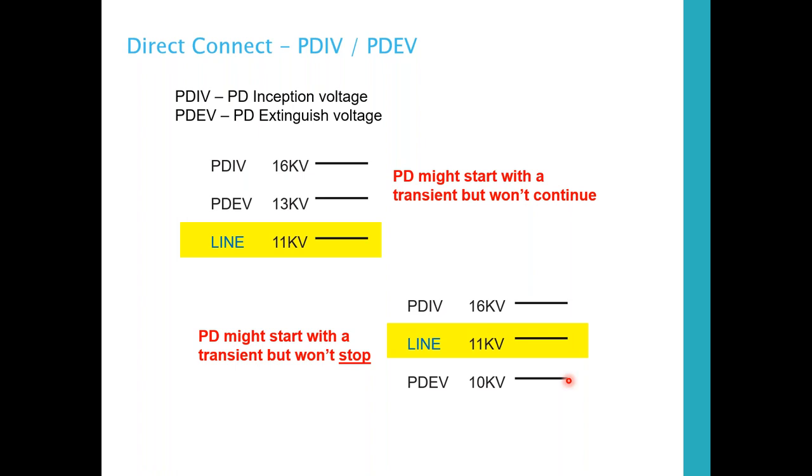And that allows me to say, okay, with this cable, the start voltage and the extinguished voltages are too close to my operating voltage level. I need to make a plan to replace this. And since I'm relatively close on my numbers here, I can get away with doing it next year.